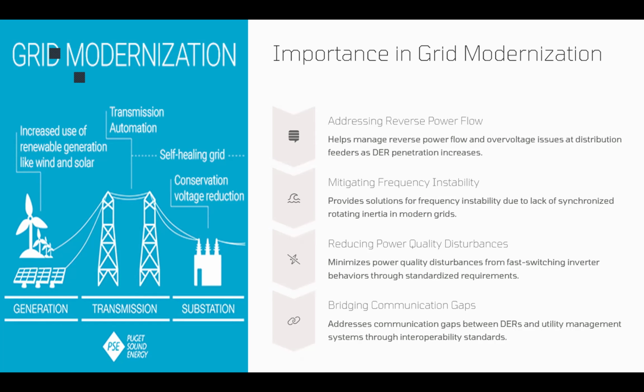Now, to meet that, the IEEE 1547 standard defines some interoperability and communication requirements. There are complementary standards like IEEE 2030 Part 5 or IEC 61850, which help to meet those communication requirements. There should be a secure remote configuration and monitoring system and firmware update. And the communication and interoperability system should support event-based dispatch, so it allows the utility to actively manage the DERs when they have a peak demand or any kind of emergency.